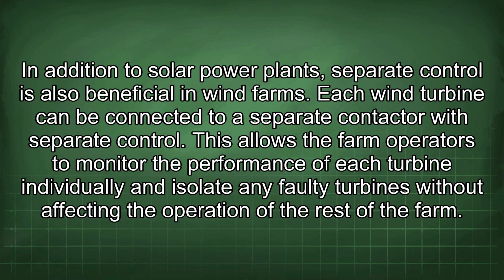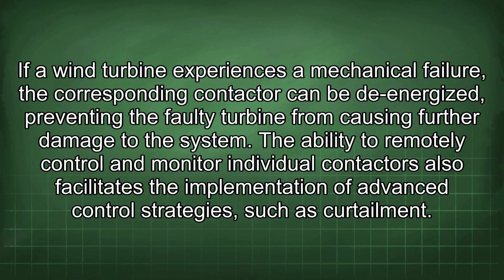In addition to solar power plants, separate control is also beneficial in wind farms. Each wind turbine can be connected to a separate contactor with separate control. This allows the farm operators to monitor the performance of each turbine individually and isolate any faulty turbines without affecting the operation of the rest of the farm. If a wind turbine experiences a mechanical failure, the corresponding contactor can be de-energized, preventing the faulty turbine from causing further damage to the system.